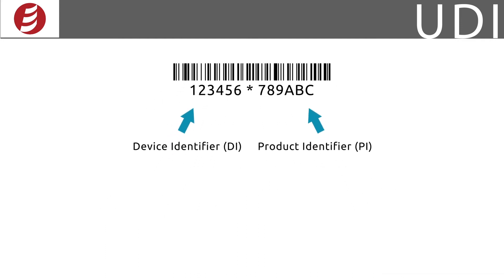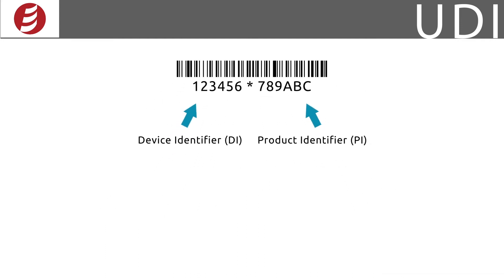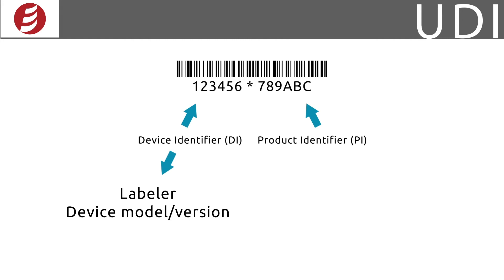The DI portion is what is submitted to the GUDID. It identifies a labeler and the specific version or model of the device. If a new version or model of the device is created, a new UDI is required.